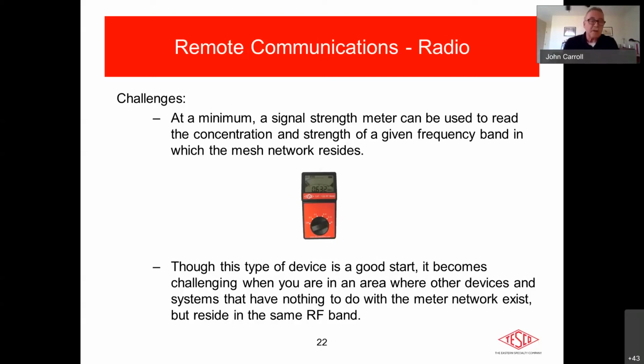And the problem they were having was the utility had installed AMI technology some years before, and this was 45, nearly 50 miles away from the headquarters, so it was quite a stretch for them. They were getting reads every day. They were polling them, and they only required a read once a day. But the customer decided to do an installation and an upgrade on their pump jacks. And they put in a fairly intense and substantial AC/DC drive panel, which was giving them more efficiency and reducing the cost for him. But like everything else, there are sometimes unintended consequences.